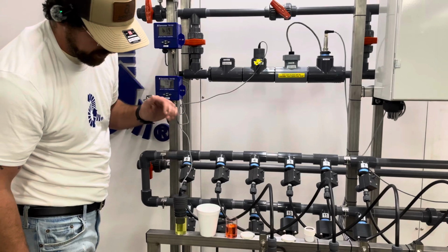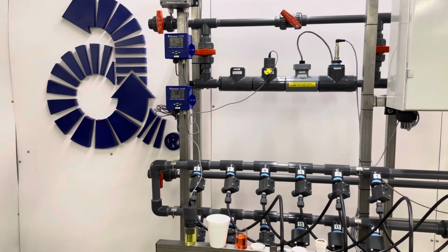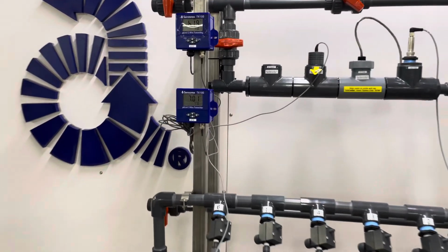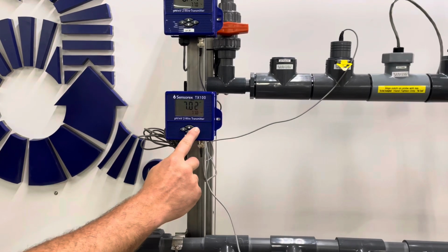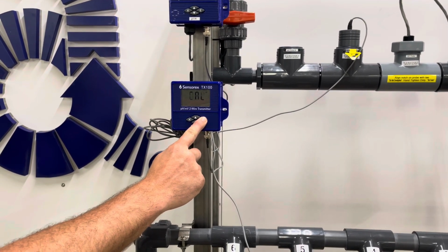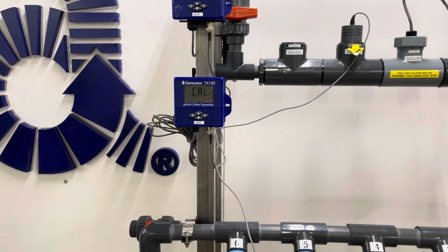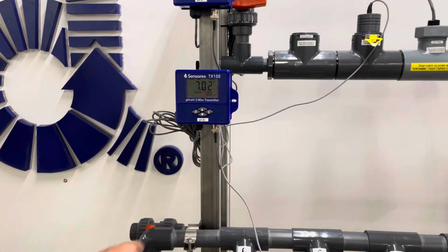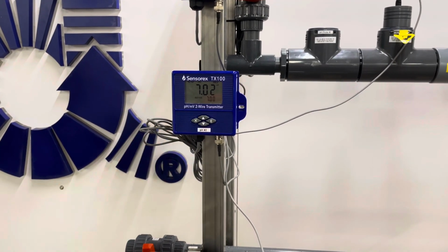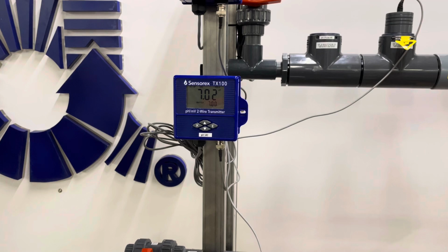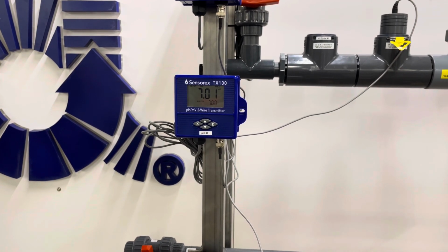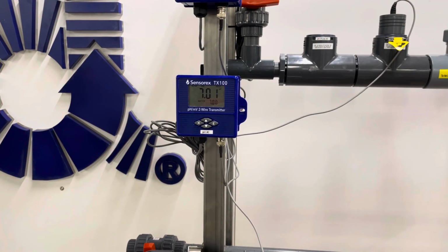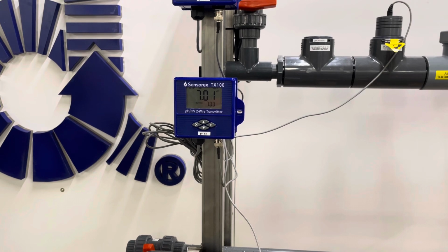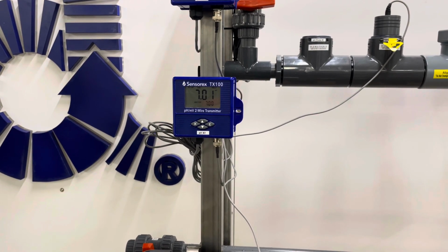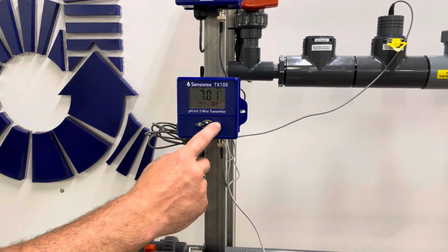Once that's complete, we'll go to our Sensorex TX100. We're going to press and hold E. Once you see CAL for calibrate pop up, you'll press E one more time. You can see it's blinking 7 in the bottom right hand corner. That's telling you to put it in 7 solution. We'll leave it there for about 45 seconds or until the top number stabilizes. Now that it's been about 45 seconds, we'll press E to lock that in.